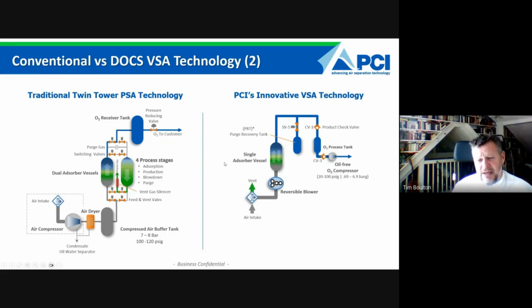The major part of this is that it is a single stage system, i.e. the pressure that you have in your pipeline or going to the high pressure booster is generated by this initial air compressor. That typically works at around 7 bar pressure. The air is then treated, it then goes through an air tank and then into one of these 2 adsorber vessels, as you can see here. And as you can see from this arrow here, this bed would be generating the oxygen.